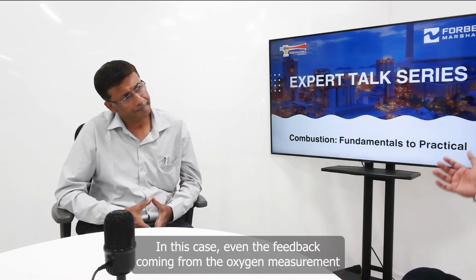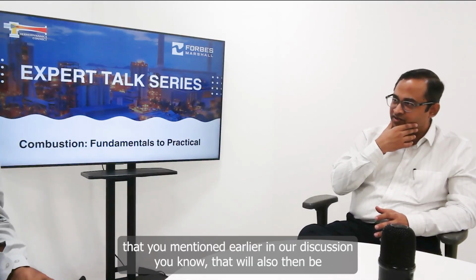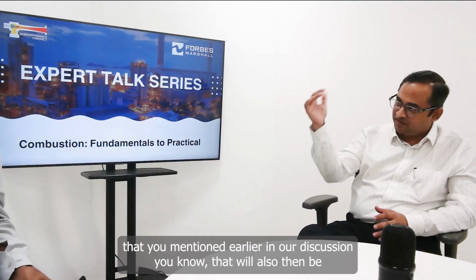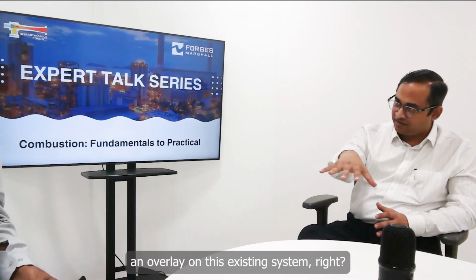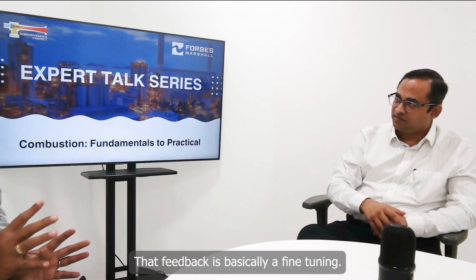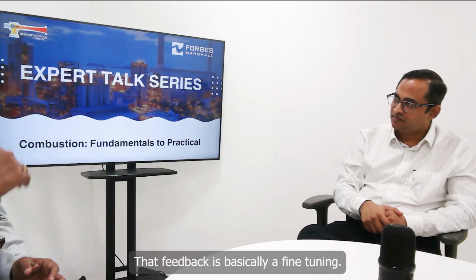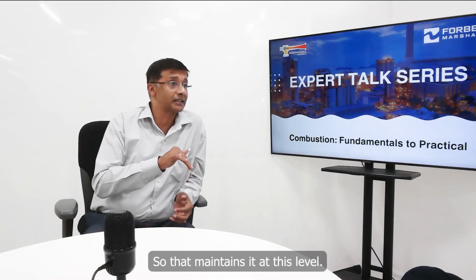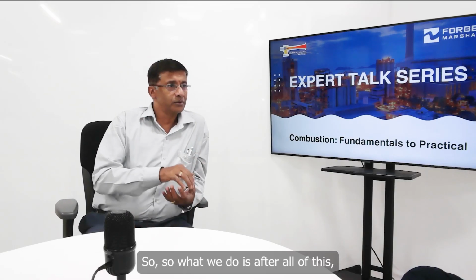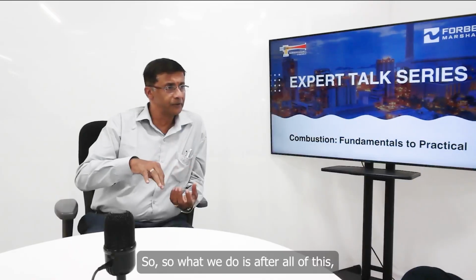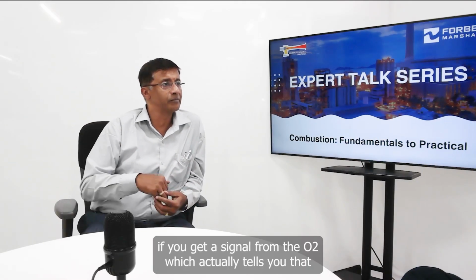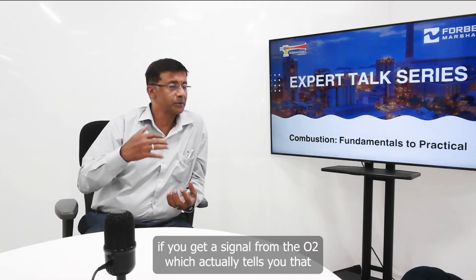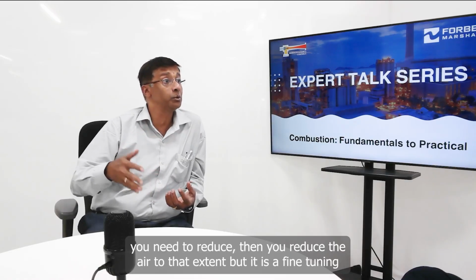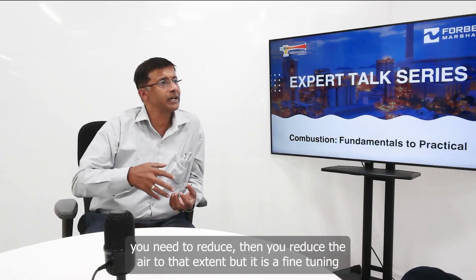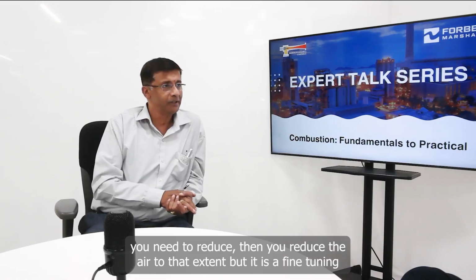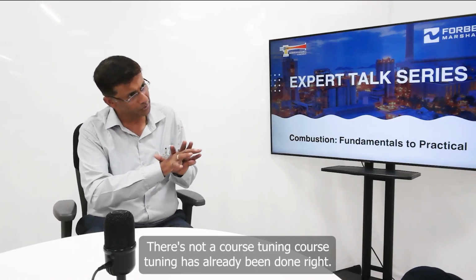In this case, even the feedback coming from the oxygen measurement that you mentioned earlier in the discussion will also be an overlay on this existing system, right? That feedback is basically a fine tuning. So it maintains it at this limit. If you get a signal from O2 which tells you that you need to reduce, then you reduce the air to that extent, but it is a fine tuning. It's not a coarse tuning. Coarse tuning has already been done.